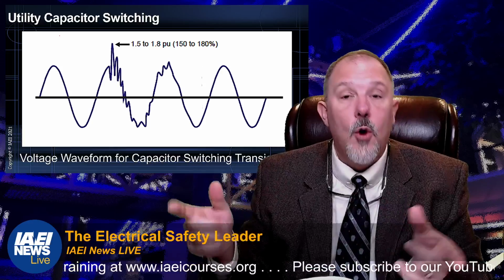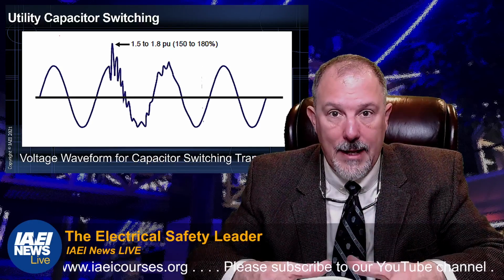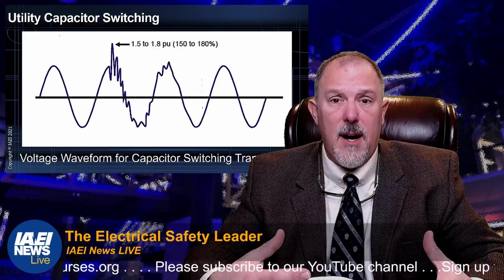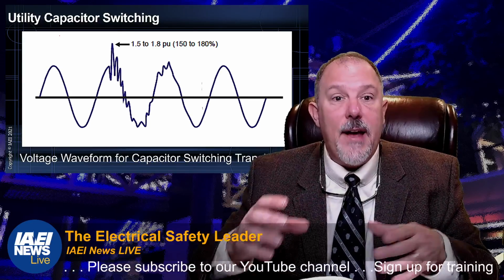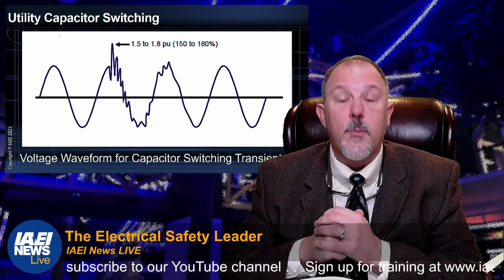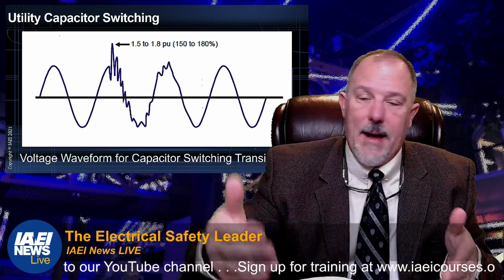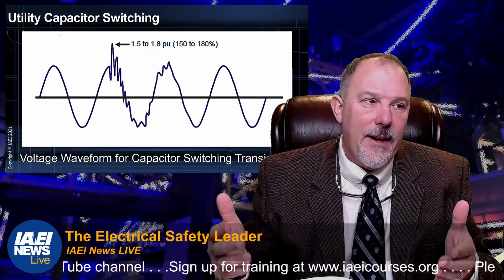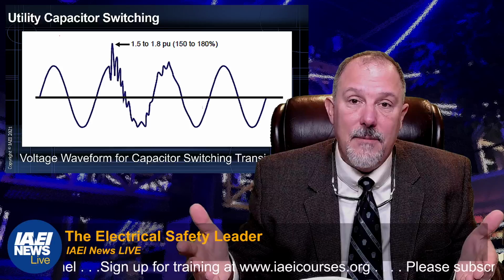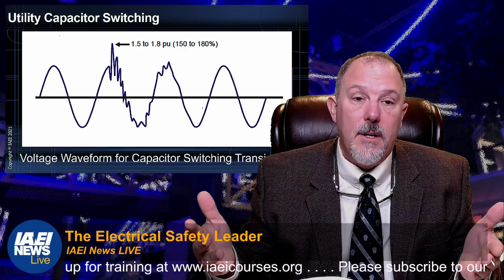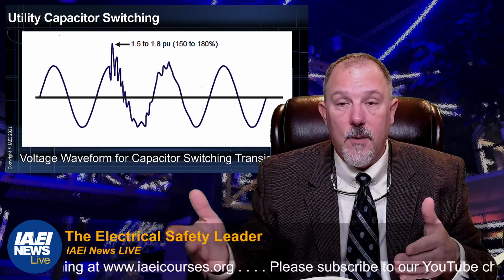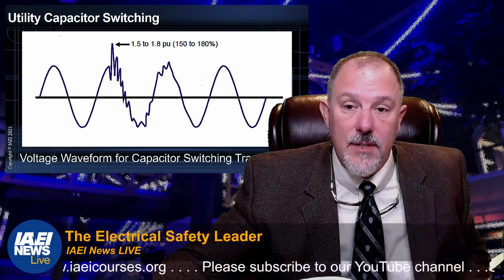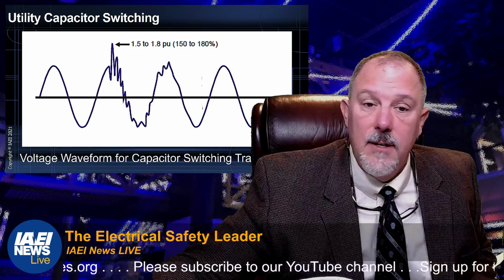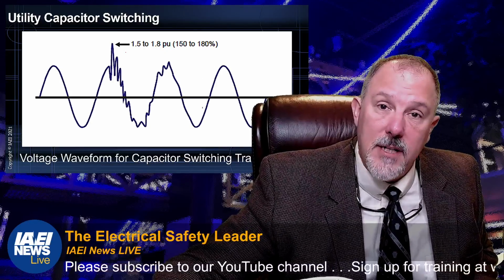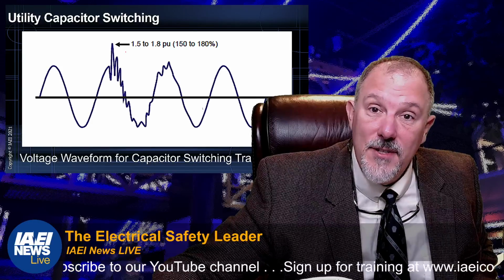Now, I'm sure once the homes were all put in and we started to load the system up, the dampening effect on this transient voltage probably did occur over time. We never went back and measured at the existing location what the events look like down the road, but suffice it to say, it was a significant effect that was probably, without protection, slowly damaging electronic equipment within these homes.